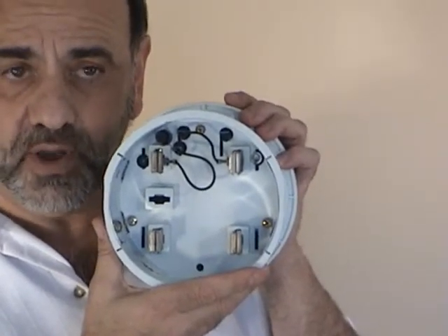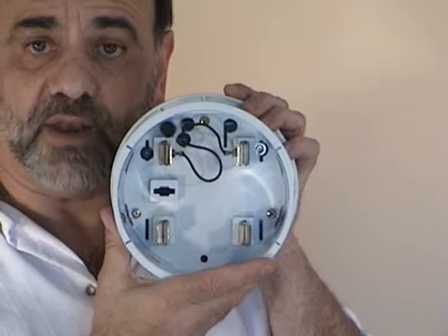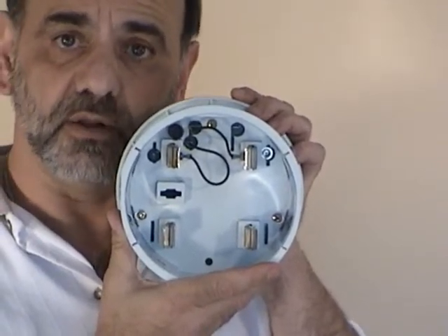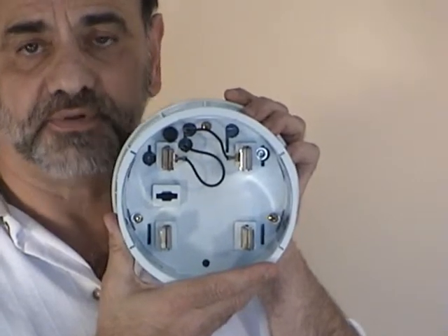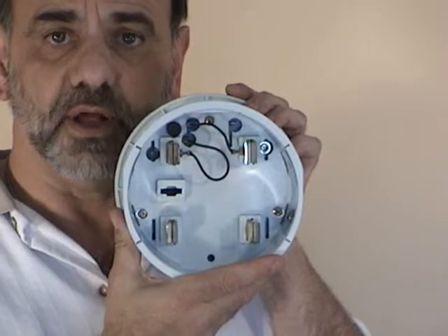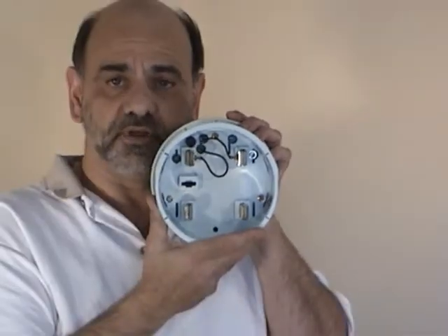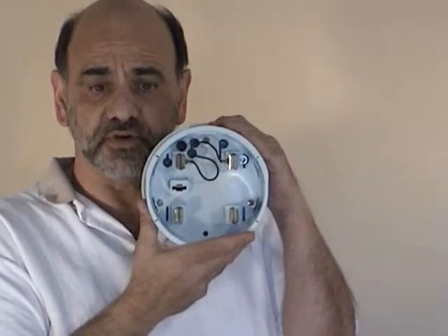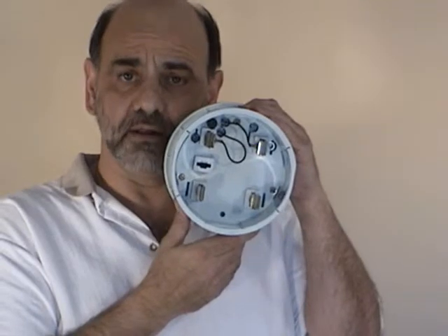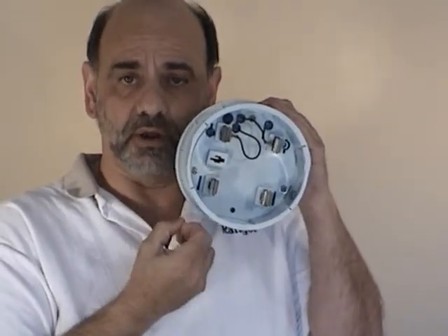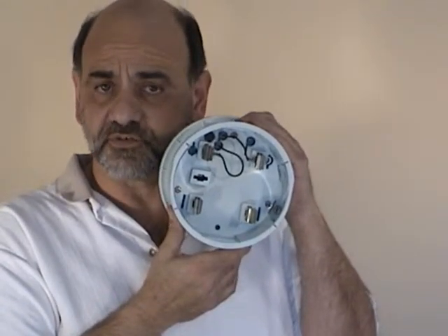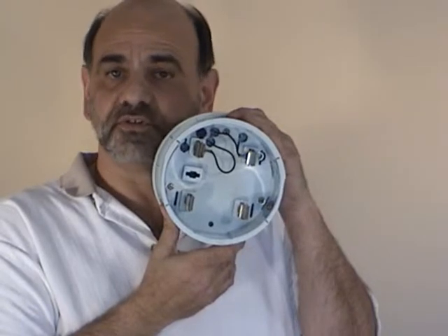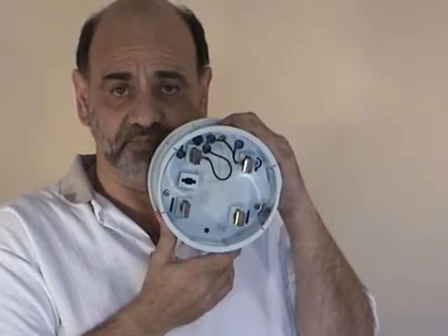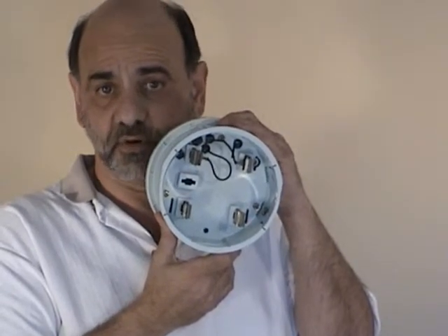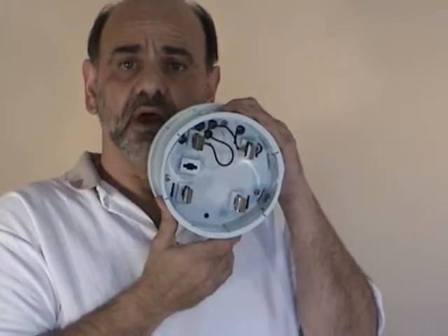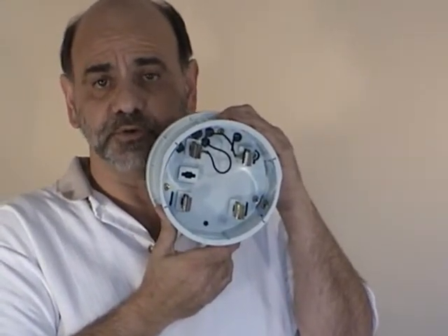We measure L1 to neutral, L2 to neutral, and we do not compute, we measure L1 to L2. And we monitor 0 to 200 amps on L1 to neutral and L2 to neutral. The current sensor that we are using in our unit is exclusively a Rogowski coil style, but it's not flexible. It's a hard coil using the Rogowski coil technology, and this allows us to read down to 0 amps. We don't tail off our accuracy at below 5 amps. We can continue to read below 5 amps all the way down to 0 amps. So if there's very little load in the house, typically at night when people are asleep and nothing's really turned on, we are still recording.